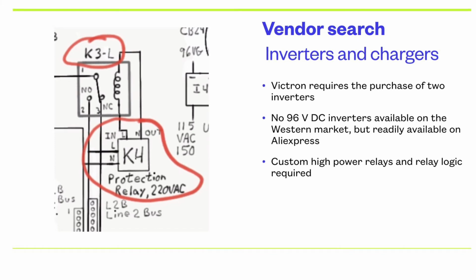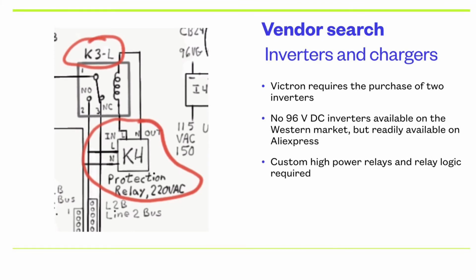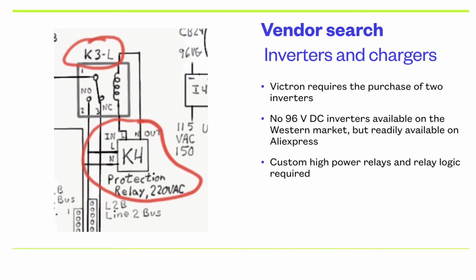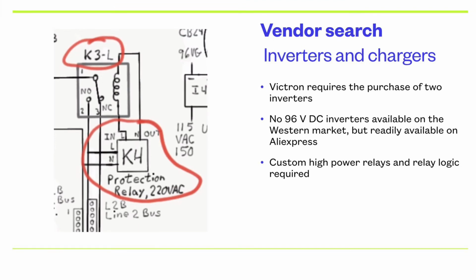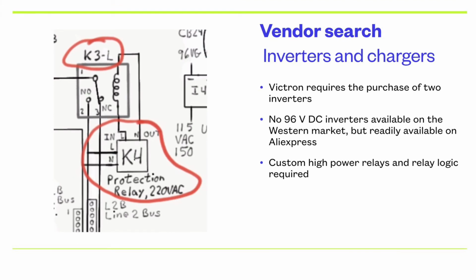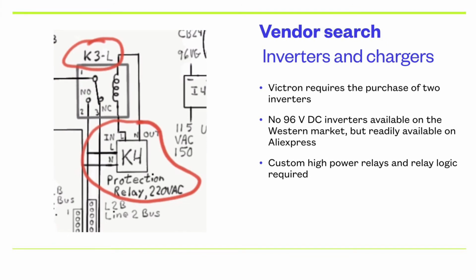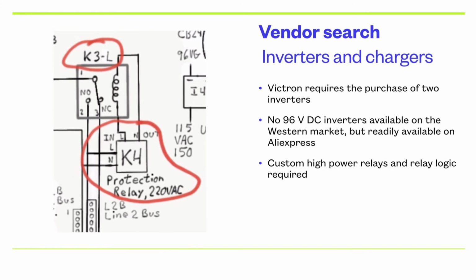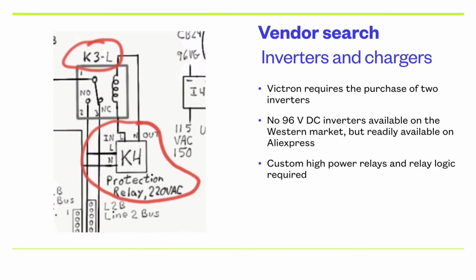I also looked at these Autotransformers, the ability to transform the power into 220. I could have done that, but I figured for a lot less money I could do it with some relays here, very simple relay logic, and just using high power relays and logic. So these high power relays, you know, $20 or less, and I did not want to use the Autotransformers to step up or step down any of the voltages because of the cost and weight of these Autotransformers, and the fact that the more heavily you load them, the less voltage you get and less efficiency you get.